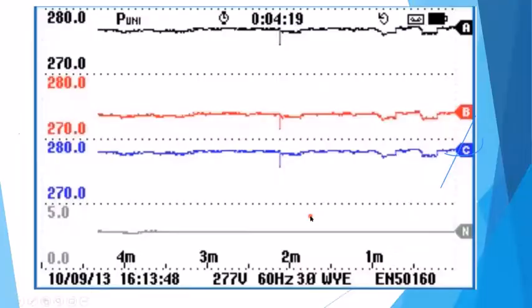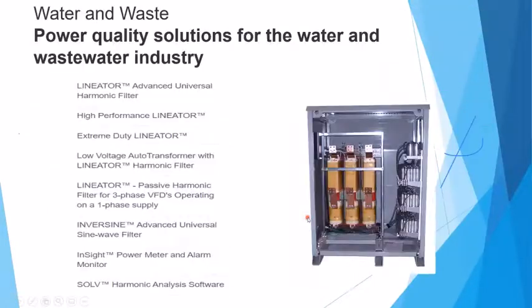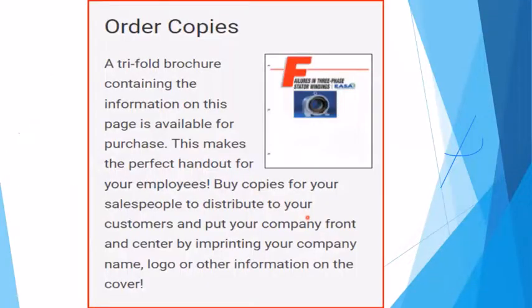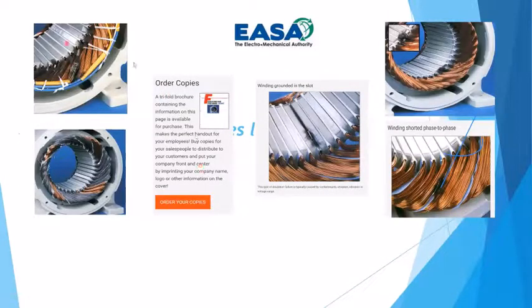The winding insulation was designed for, let's say, 1200 max peak to peak volts. Well, as soon as we get a higher potential between two phases of power, and you get this giant spike, those two want to take the path of least resistance to create an arc, and it basically creates a spark between them and burns the insulation out. So that's what you have to be careful with on the VFD, the peak to peak output voltage.